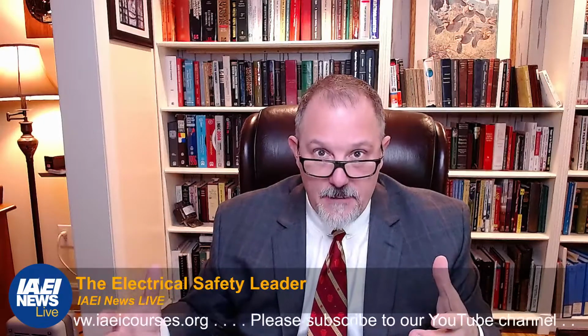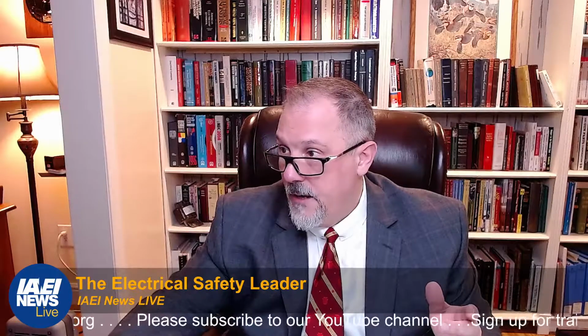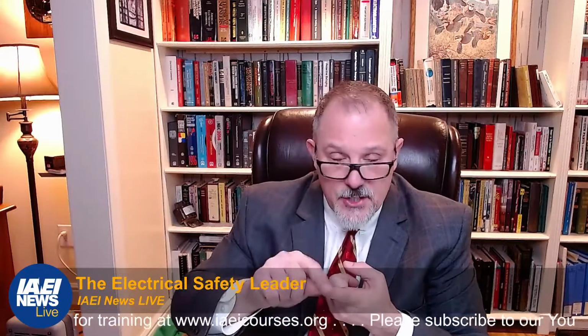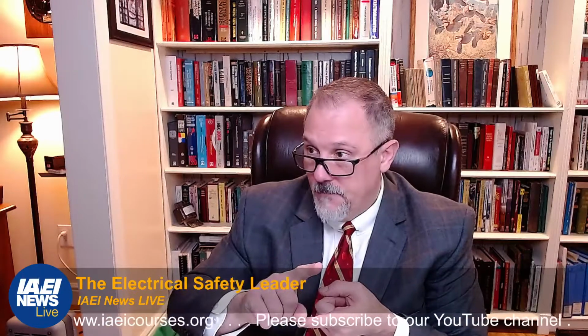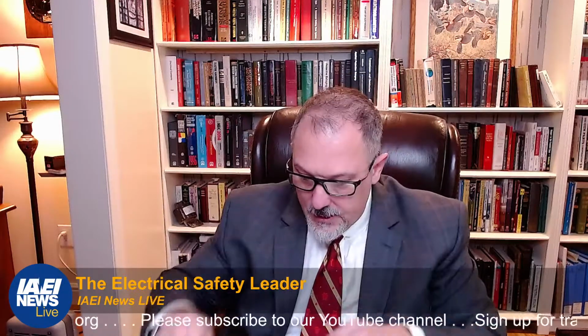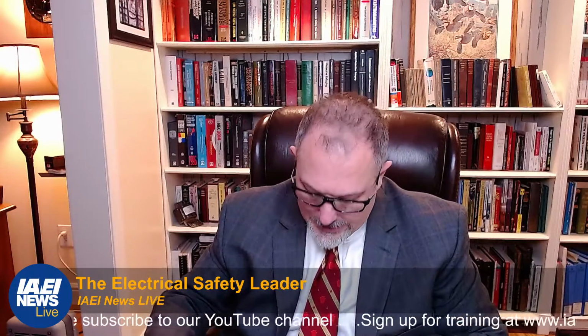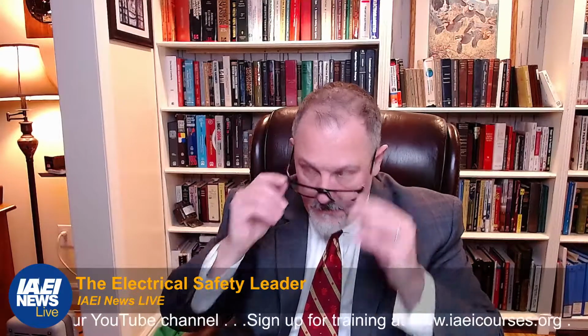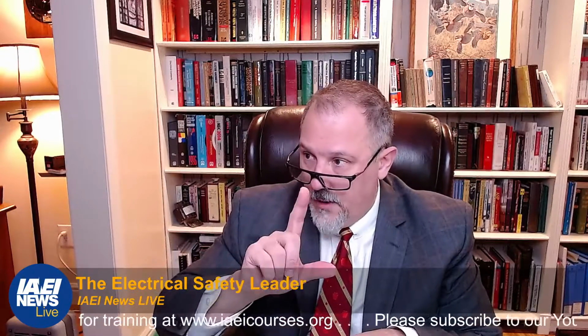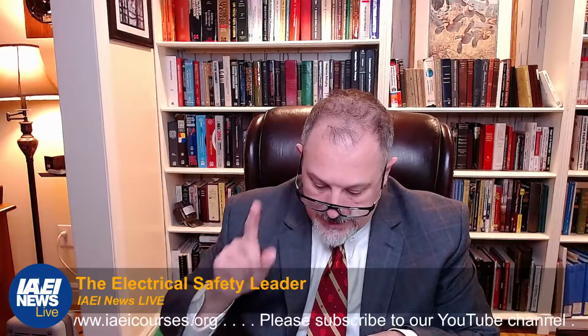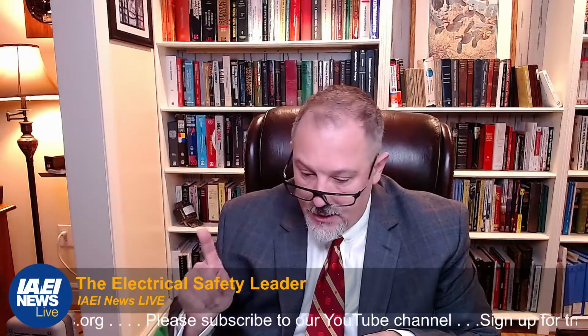110.2a is now policy. So they had a focus on policies that the employer has to establish, document, and implement: the electrically safe work condition policy that requires that hazard elimination is the first priority. I think we used that term, hazard elimination. Yes, that's 110.1 in the previous edition. So they still maintain that your number one priority is hazard elimination. And they said that it has to comply with 110.2c, which is when required.